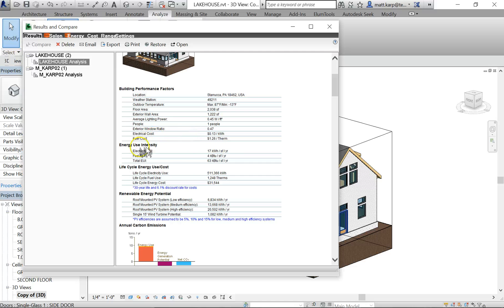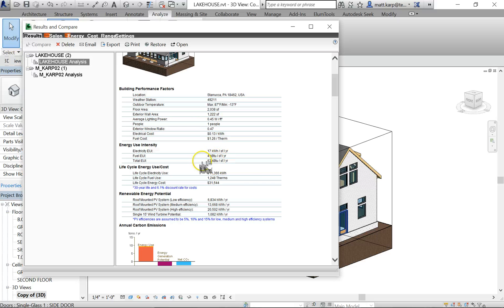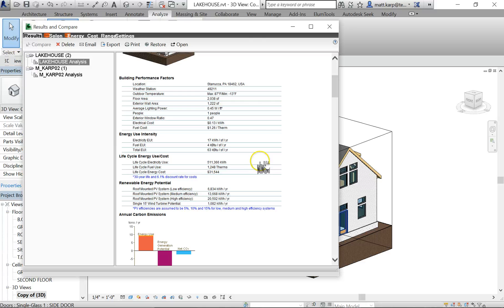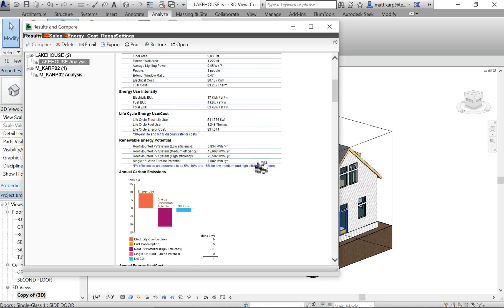What this is, is it gives you your energy use intensity: electricity, fuel. So fuel is about 4 thousand BTUs per square foot a year, and electricity, it's about 17 kilowatt-hours per square foot per year. And then a total. And this is your total building energy use. This is important because this one is saying how much energy you're using without putting a dollar amount to it, because we really just care about lowering energy use, not necessarily always lowering costs.